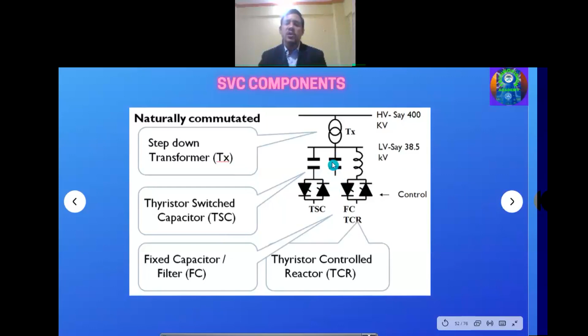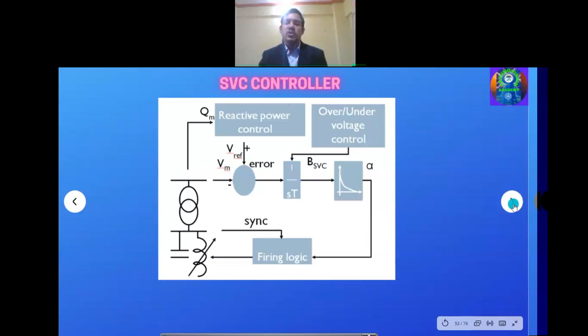This is a controller which is used to connect this static var compensator with the power system. We know that we connect with this step down transformer, which connects our SVC, and then for firing, reference voltages are also given, some maximum voltage, reference voltage, whatever error is coming from the system, maximum reactive power as an input, then under or over voltage limits are also set into this controller. In this way, by using certain controllers, we finally generate the firing logic, and according to that the parameters of these SVCs are varied, and accordingly it will inject or absorb into the system, and in this way we will maintain our system. So this is all about the SVC controller.